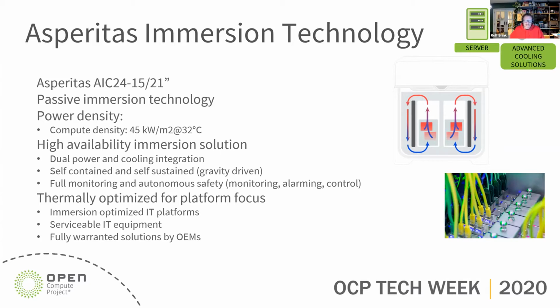These systems are placed in the middle part of the tank. The heat drives the flow through density differences: heat generates a lower density liquid which wants to float, so that liquid moves towards the surface. On the sides of the IT equipment, we have water-cooled heat exchangers connected directly to the facility water circuit.